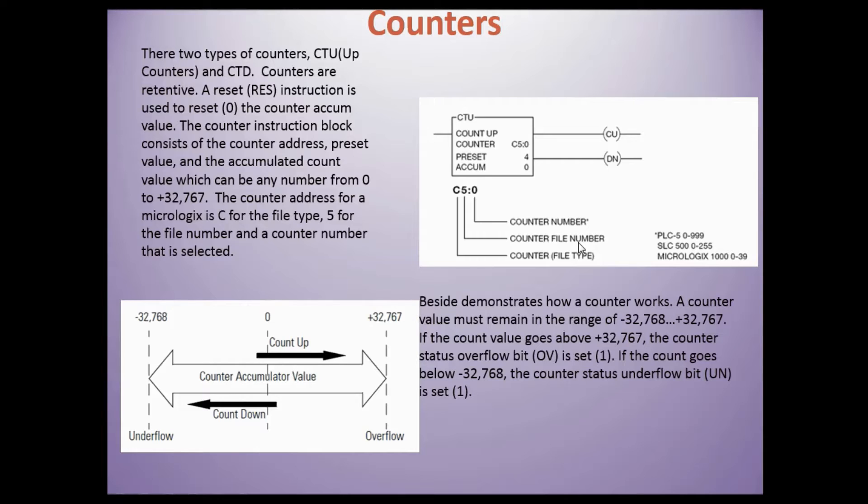This example demonstrates how a counter works. A counter value must remain in the range of negative 32,768 to 32,767. If the counter goes above 32,767, the counter status bit OV is set to 1. If the counter goes below negative 32,768, the counter status underflow bit is set to 1.